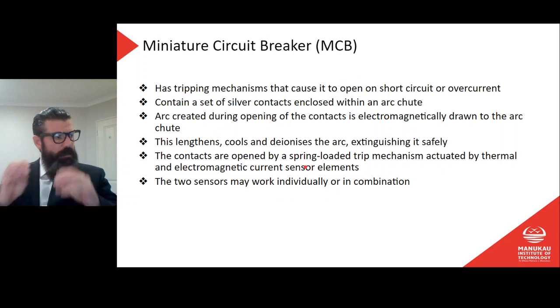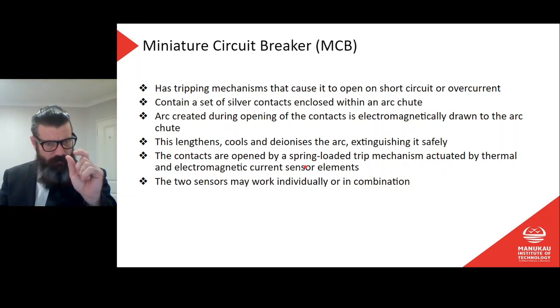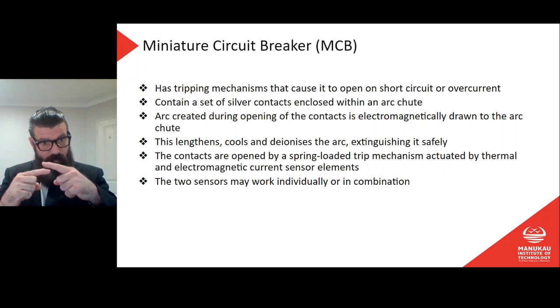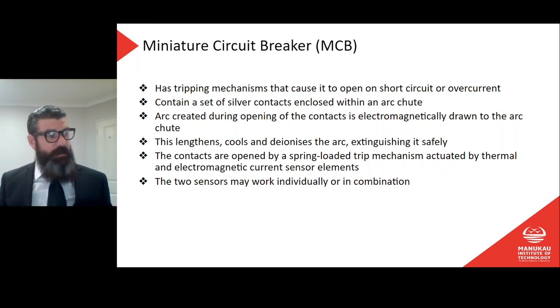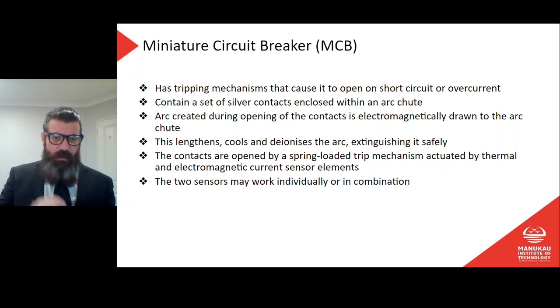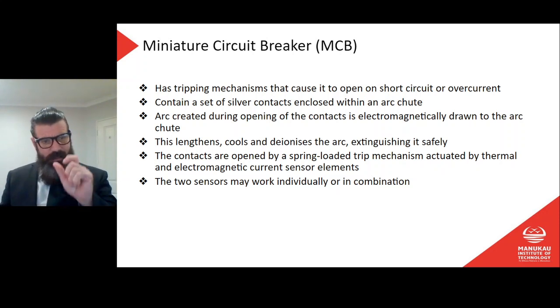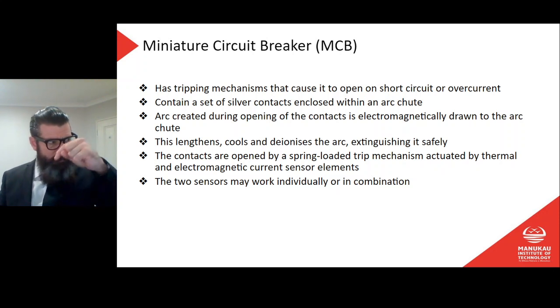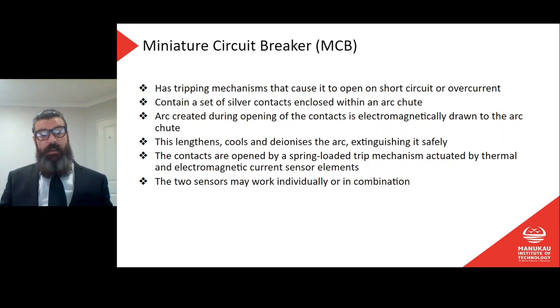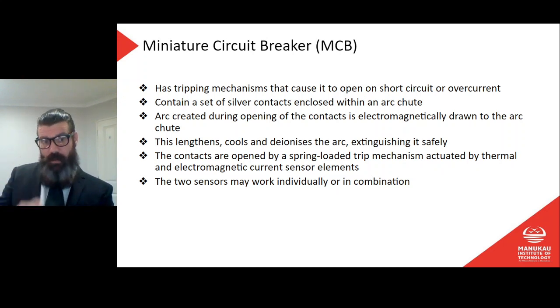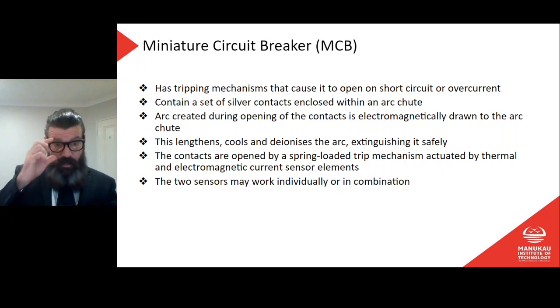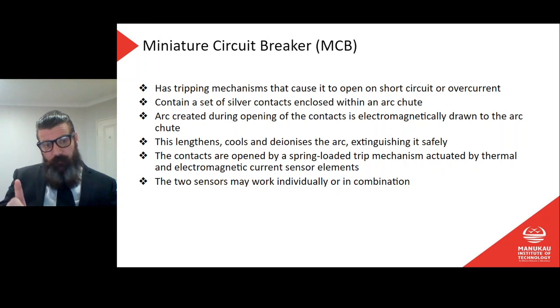Cool. What does it mean? Inside of an MCB, we know this stuff, right? We have our thermal, which senses overheat, so a bimetal, and as we have an overcurrent, it heats up and will slowly move away, which activates the tripping mechanism. Alternatively, when we get that very high short circuit current, it is going to travel through a solenoid, essentially a small solenoid inside there. That solenoid is a little electromagnetic piston, right? So that high current flowing through creates a large magnetic field. A small current flowing through there won't do anything. The magnetic field's not big enough. But when we get a large magnetic field through that solenoid, it's going to move that piston, and that piston hits the tripping mechanism and it trips off.